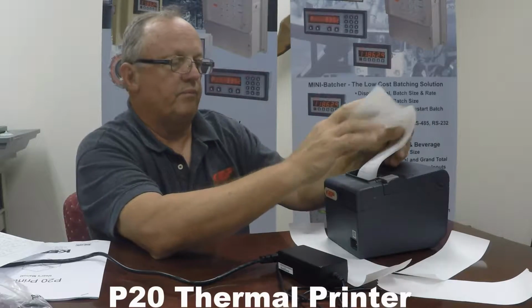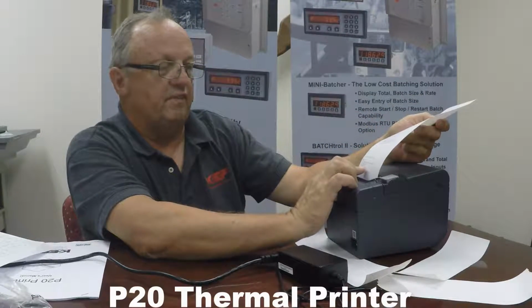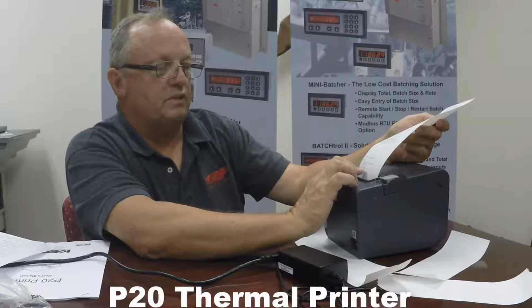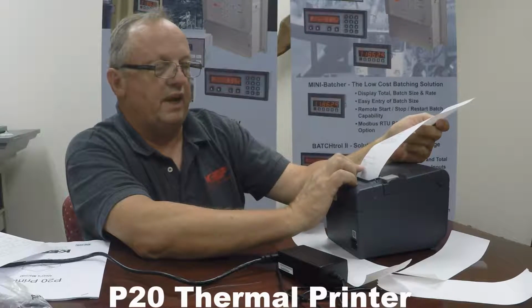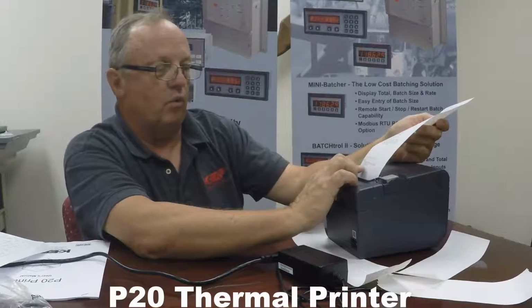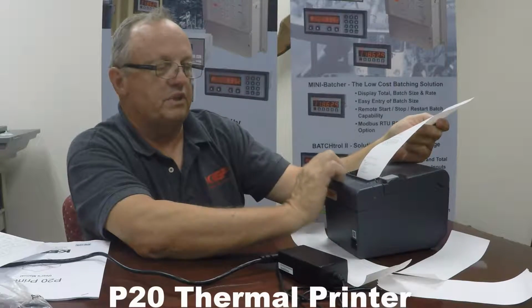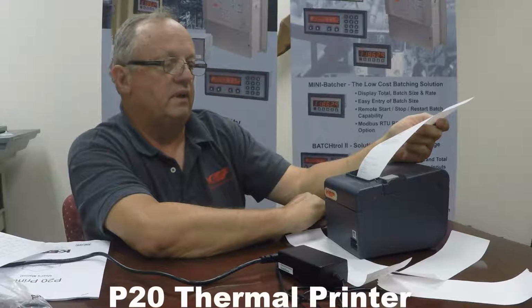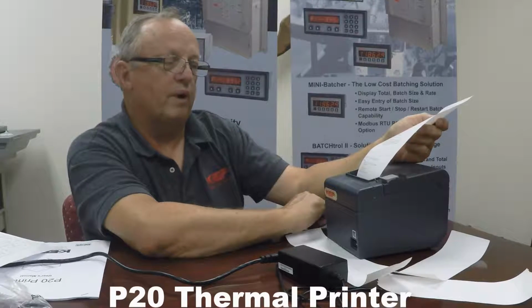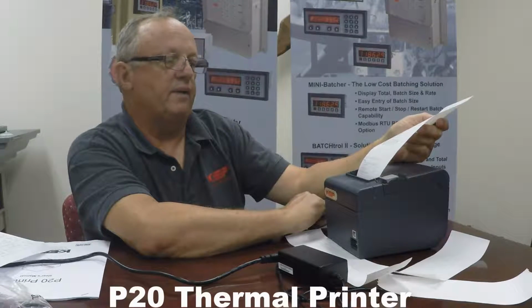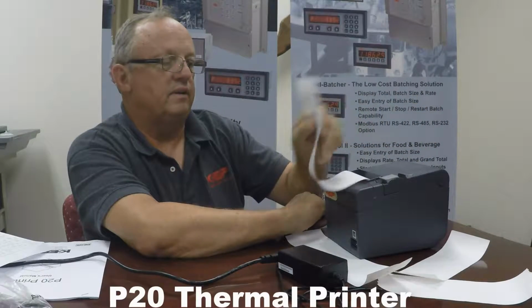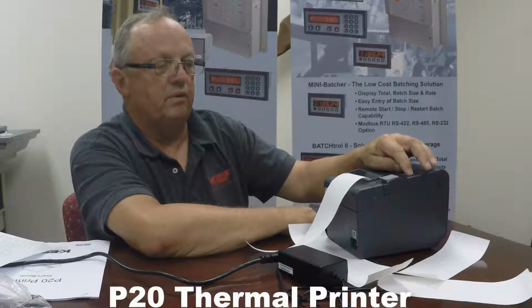Now at this point, it's giving me the options of either going back to a previous menu or changing either the baud rate, the parity, the handshaking, the data bits, or the data receive error symbol. We're going to start with the baud rate. In this case, that's going to be 1 quick depression to select baud rate, followed by a long selection to let it know that that's what I want to do.